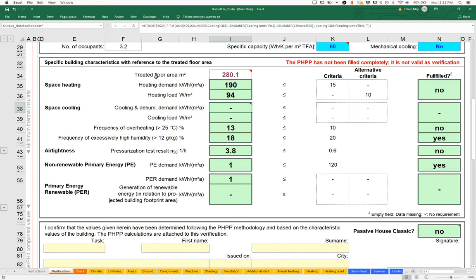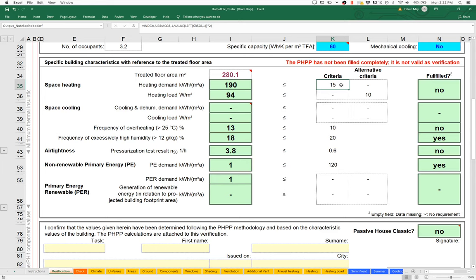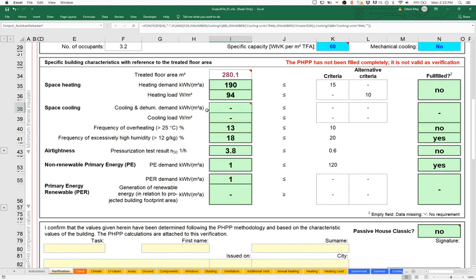We have an annual heating demand of 190 kilowatt hours per square meter per year. If you look over here on the right, for Passive House certification to the PHI Classic international certification, our target would be 15 kilowatt hours per square meter per year. We still have a lot to detail, and 15 is not always our target. If it was a low energy building, our target would be 30. If it was a renovation in a cold climate like New York, our target would be 20. But in any event, our heating demand looks very high compared to our target.